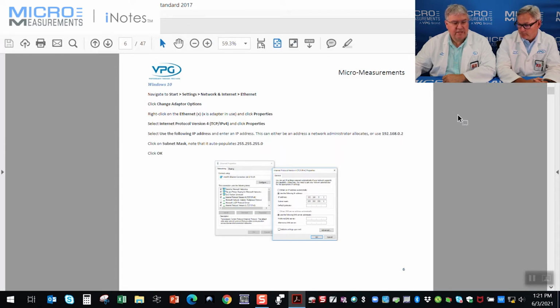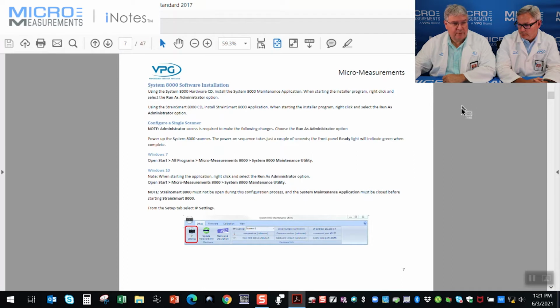The next step in the guide deals with the maintenance utility program. This really needs to be run before any connectivity is attempted with StrainSmart. A lot of folks jump straight to StrainSmart, and sometimes when people move the software to another PC they forget about the maintenance utility, and then we get regular calls saying they can't connect. So in this video, we're going to invest most of the remaining time into this maintenance utility to show not only how to establish a connection, but also the opportunity to update firmware and perform a system calibration using an NIST traceable device.